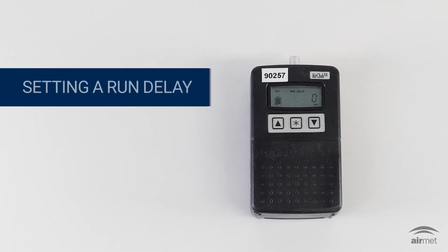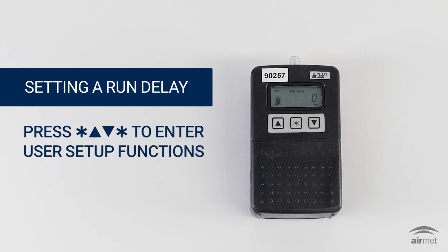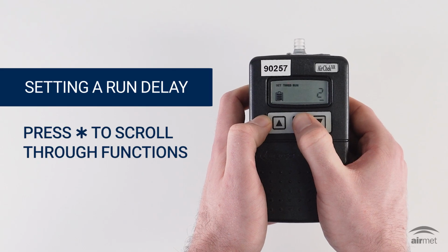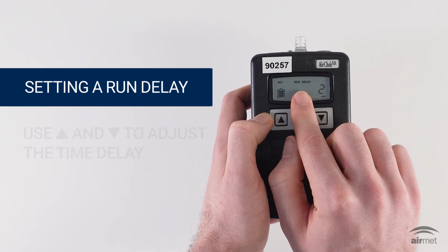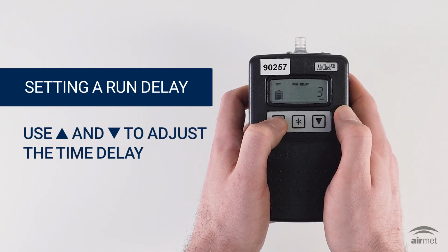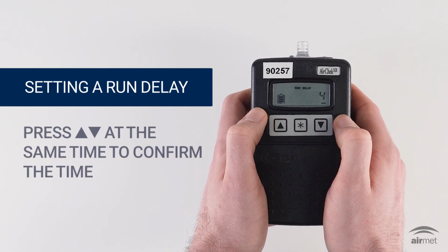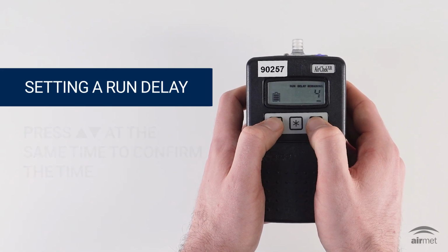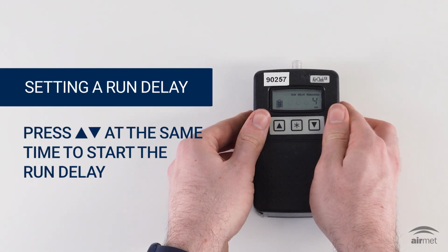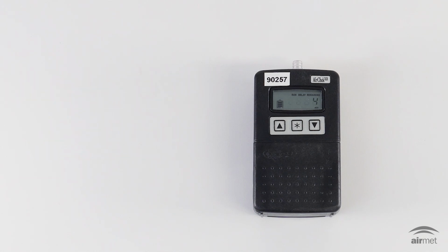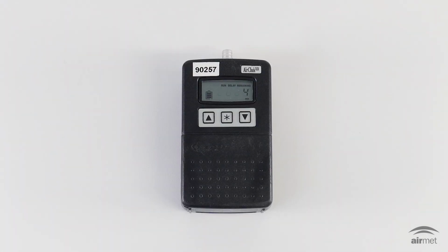The XR5000 is also capable of a run delay for DPM or asbestos sampling events. To set a run delay, go to the user setup and scroll until you find set run delay. Using the up or down arrow, set the time delay minutes. Press the up and down arrow keys together to accept. Then pressing up and down together on the main screen will initiate the run delay. The pump will then wait and start running automatically once the delay has passed.